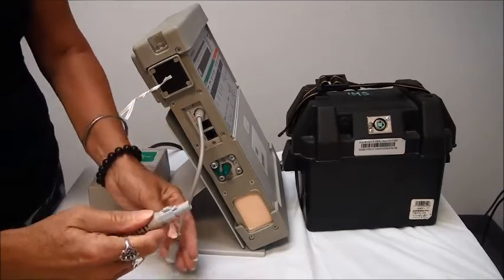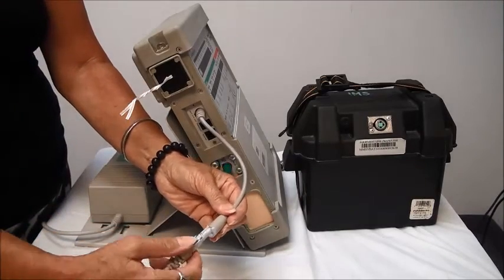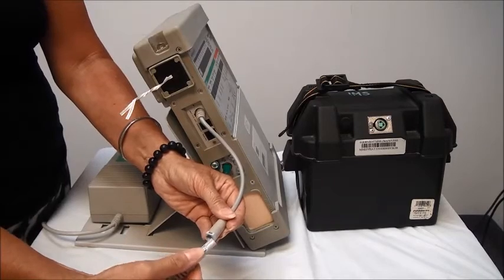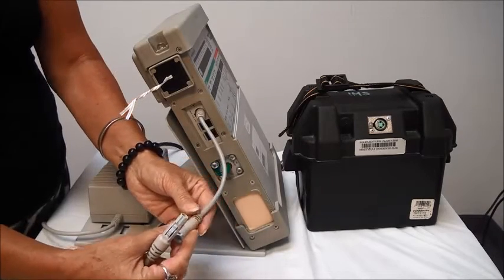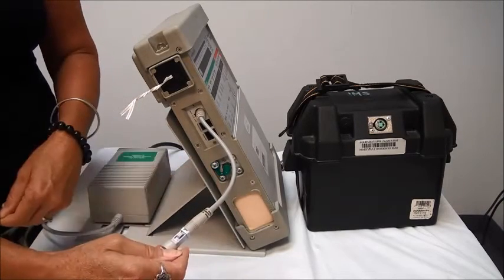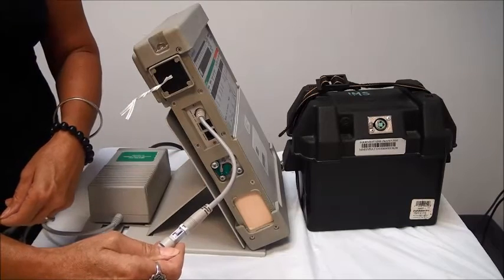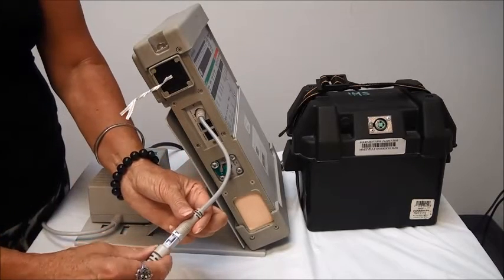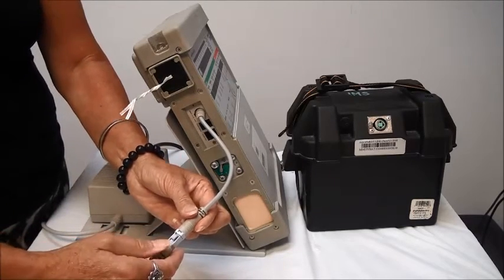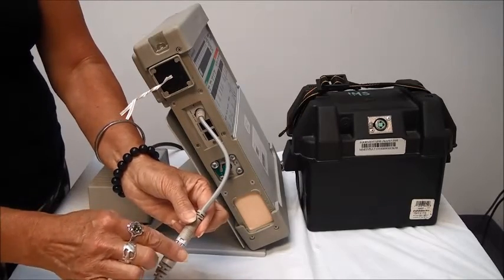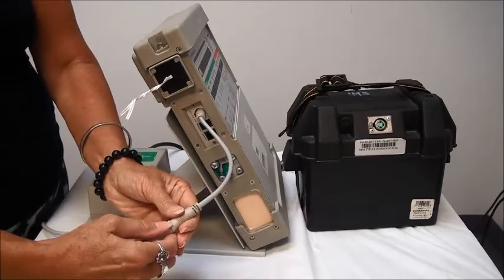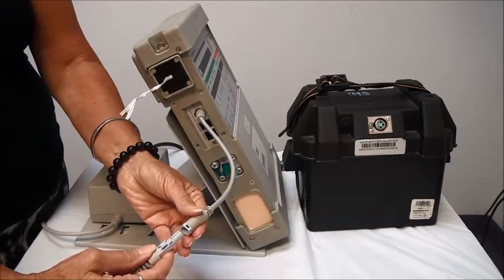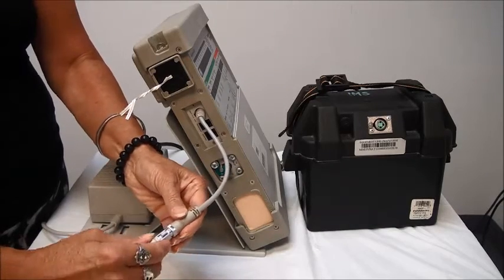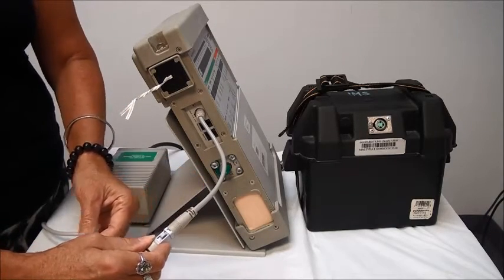Alright, if you take a look, you can see the connection. There's a little push button on the power cord side that will just pop right into the ventilator. Now when disconnecting this, you want to be careful not to pull. If you do, you can break your little connector here, and then the connector won't stay firmly connected. So you need to be very careful when disconnecting.